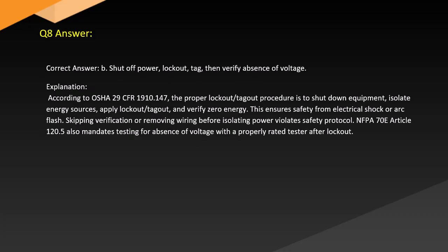Answer. Correct answer: B. Shut off power, lockout tag, then verify absence of voltage. Explanation. According to OSHA 29 CFR 1910.147, the proper lockout-tagout procedure is to shut down equipment, isolate energy sources, apply lockout-tagout, and verify zero energy. This ensures safety from electrical shock or arc flash. Skipping verification or removing wiring before isolating power violates protocol. NFPA 70E Article 120.5 also mandates testing for absence of voltage with a properly rated tester after lockout.